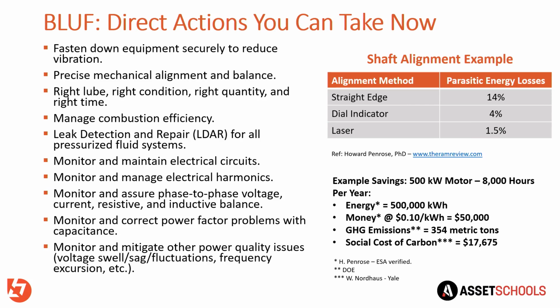So we need to manage that with what are called harmonic filters. Now there's 2 types of harmonic filters. There are active harmonic filters and there are passive harmonic filters. So if you have a harmonic in your system, you can actively filter that by putting energy in the system that's 180 degrees opposite of that harmonic. Does that make sense?